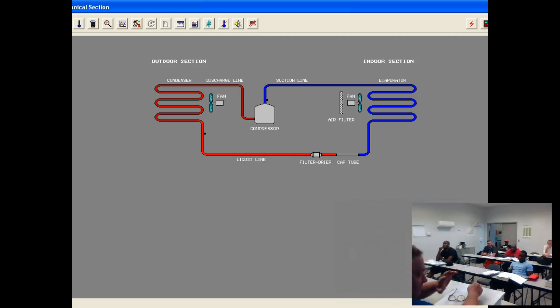do you know? There's no air conditioning God that comes down and says, good job, son. You have to just kind of figure it out. It's working right. Probably don't want to sit around for an hour to see if it's cooling. So a lot of times you can speed it up to a 60-to-1 ratio, and you can see it cool, the space temperature come down, cut off, it'll cycle. That's probably a good indication it's doing what you want, okay? A lot of people forget that they left it on 60-to-1 and they can't see pressure switches that open and stuff because everything's happening so fast. So you speed it up, but you might want to remember to slow it down.